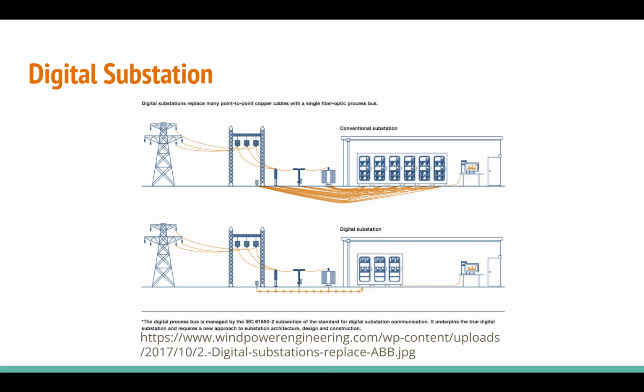We very commonly separate our power systems into primary and secondary technology, or primary and secondary voltage and current. In this image at the top, these are power lines, and here we have measuring equipment. We have current transformers, which allow us to read the amount of current on the lines, and voltage transformers, which allow us to read the amount of voltage. When that information goes through the current transformer and voltage transformer, it comes out as a much smaller signal than what was put in.